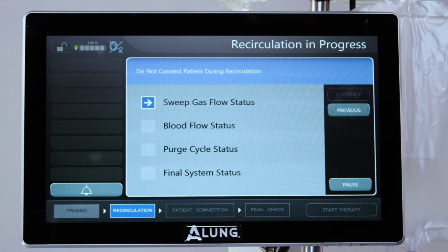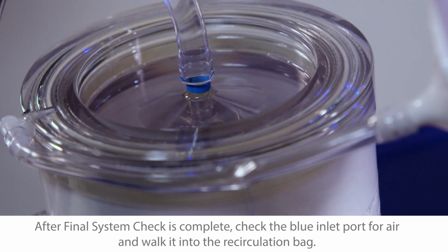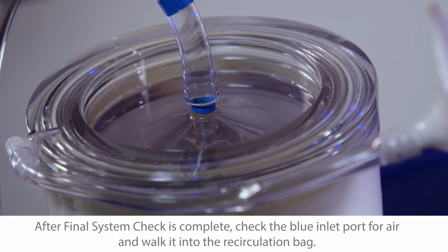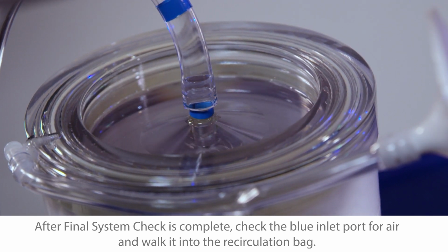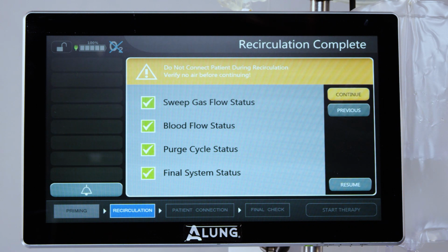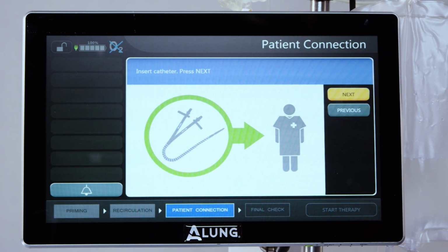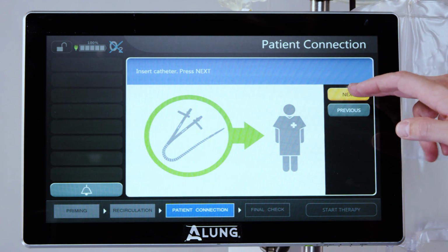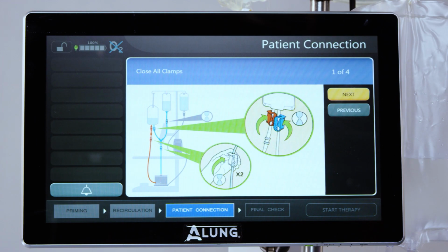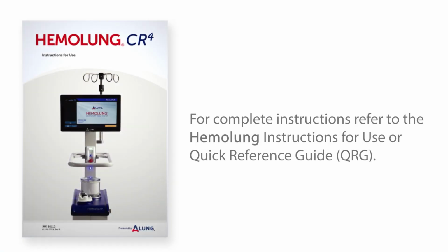Press Next to start the recirculation process. Check the blue inlet port on the cartridge for air. If found, walk it into the recirculation bag. Once the self-test completes, press Continue. The pump will now run continuously until the patient is ready to be connected. Pressing Next will stop the pump and display instructions for connecting the patient. For complete instructions, refer to the HEMOLUNG CR4 instructions for use.